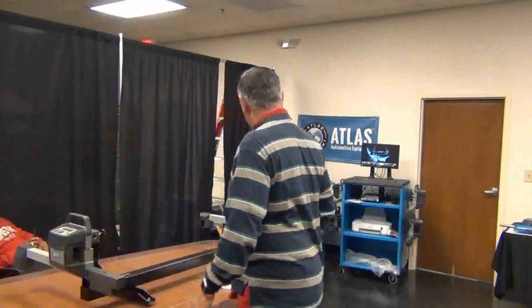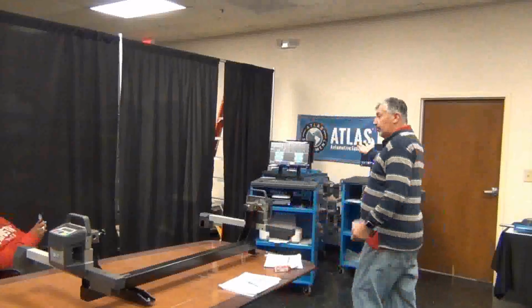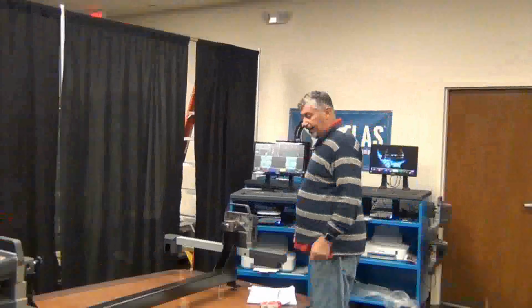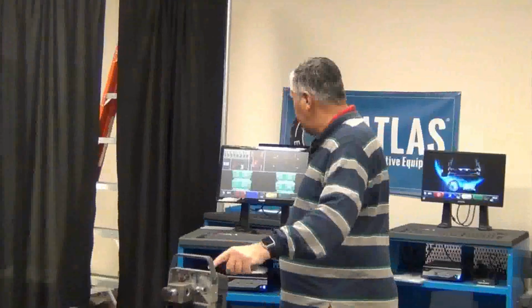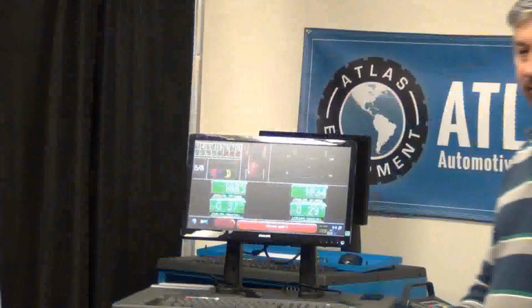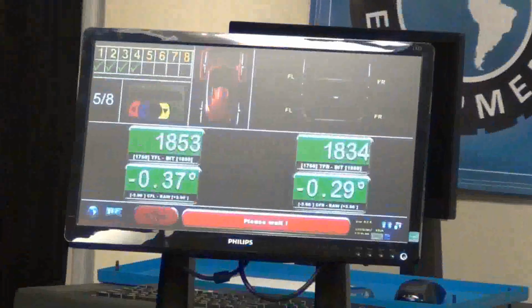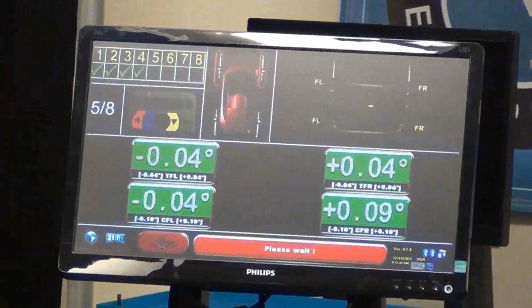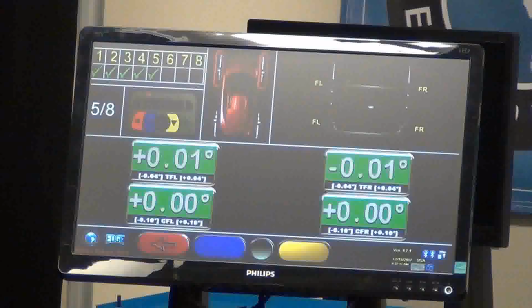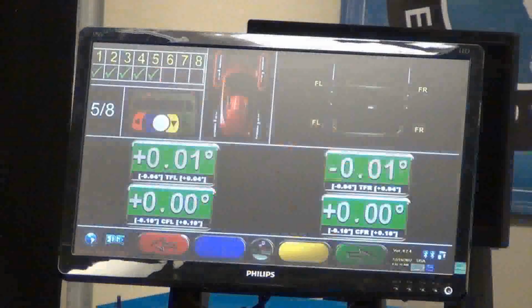There we are. Now set everything up. As you can see, it is in the green, which is pretty well calibrated as it is. So now push the F5 button and allow the machine to find its 0 once again. While the machine searches for 0, which is actually achieved, position number 5 of 8 is now complete.